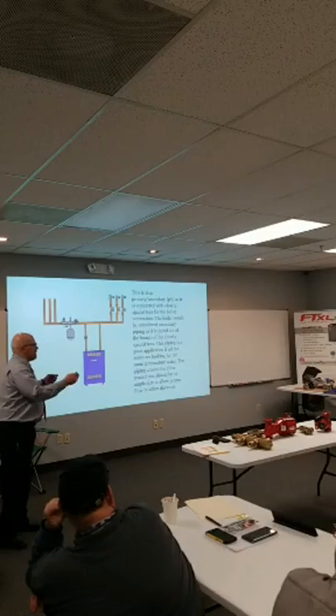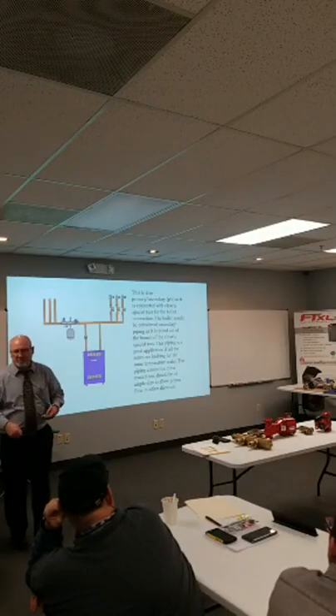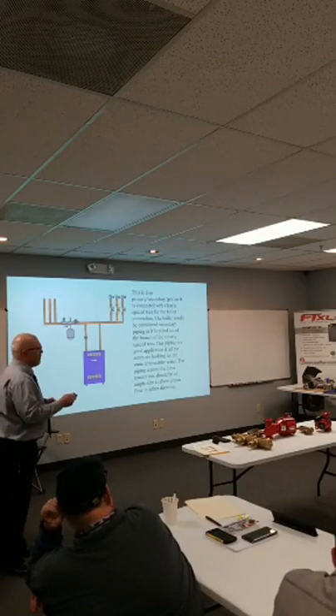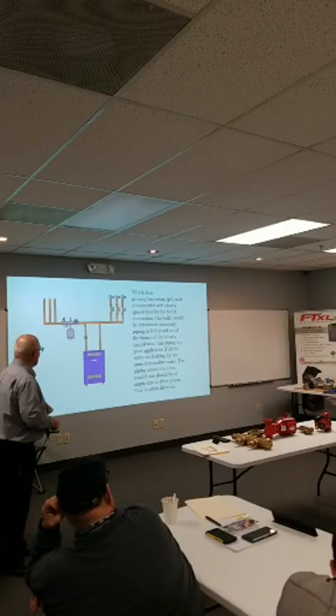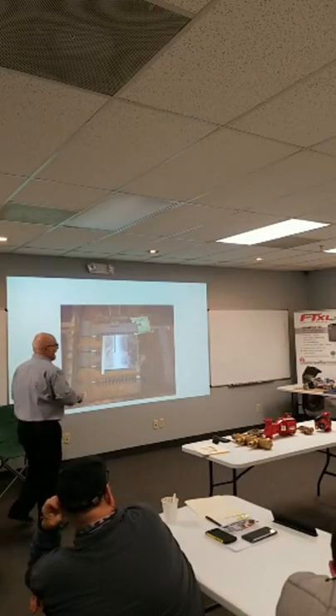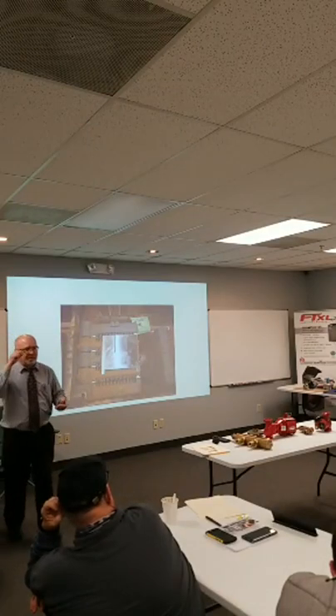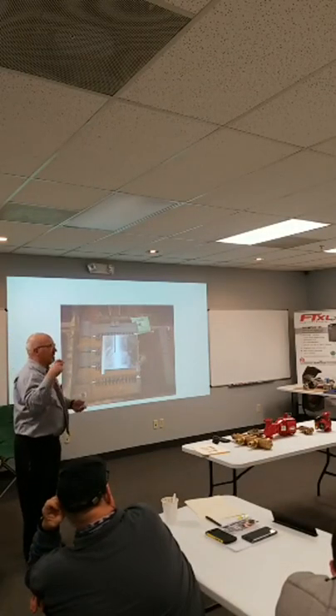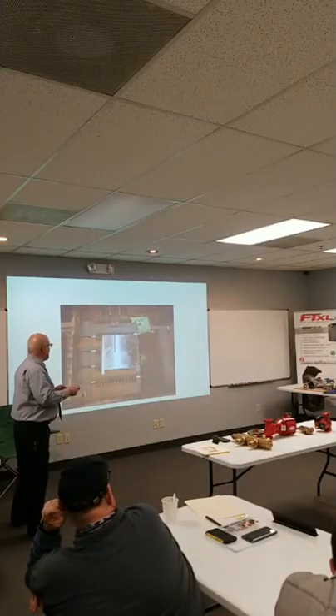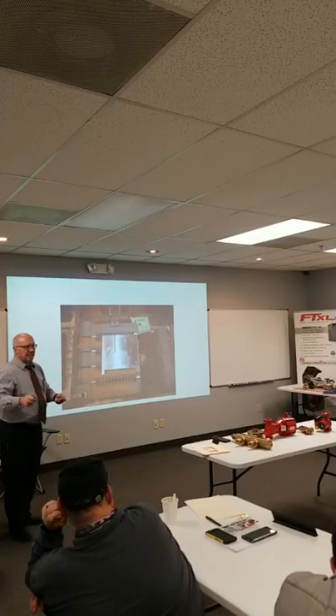But this is just showing you that when we first started introducing primary, secondary, we kind of did it and it worked, but it didn't work exactly as we thought it was going to. But that's how we pipe standard everyday cast iron sectional boilers, 80% efficient. Series loop, monoflow systems, zones, right? Pretty simple. One pump circulating all through.